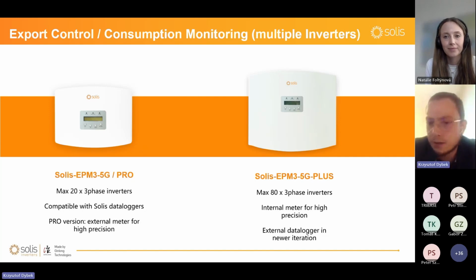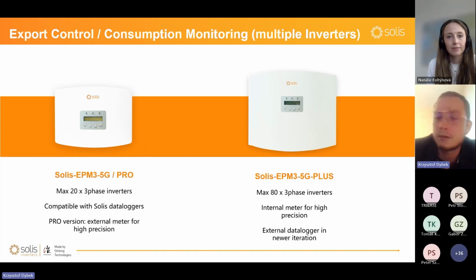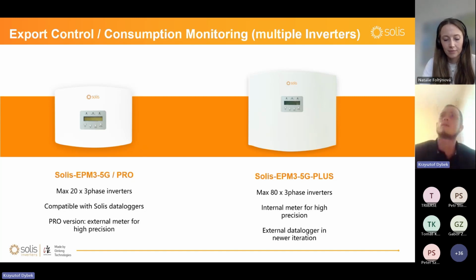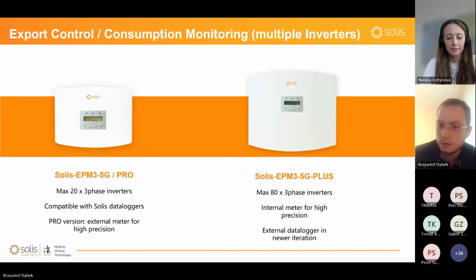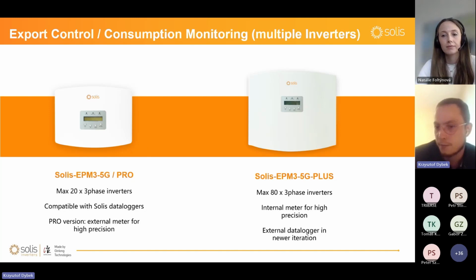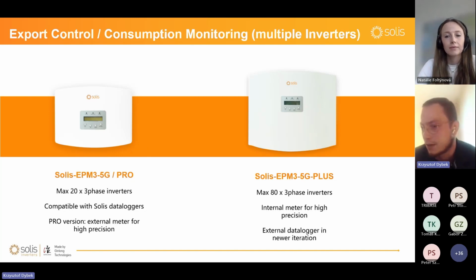Okay, chassis is also smaller, but it's easier to install everything. As I said, there is no data logger inside, but you can add it separately. S2 logger with 4-pin port. I will describe a little bit more about loggers and differences between them later on. So Pro version will have possibility to be compatible with S6 series hybrid, the newest hybrid, as well as the grid type, but only Pro version of EPM, not Plus. So you can put there both type of inverters in cascading scenario.